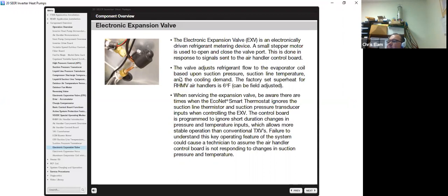When servicing the expansion valve, be aware that there are times the EcoNet smart thermostat ignores the suction line resistor and transducer inputs when controlling the EEV. The control board is programmed to ignore short duration changes in pressure and temperature, which allows for more stable operation. Failure to understand this key operating feature of the system could cause a technician to assume their air handler control board is not responding to changes in the suction pressure and temperature.